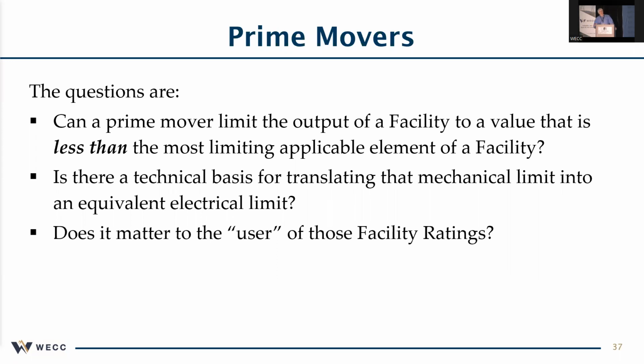Somebody buys a diesel generator set, and with a generator on it, it's rated. They're matched pretty close down at sea level. Then they install the thing up at 7,000 feet, and you lose 3% of your capacity for every 1,000 feet of elevation. So all of a sudden your prime mover is going to be 21% less than what the generator is rated at. And that's a real limit. You're not going to beat that.